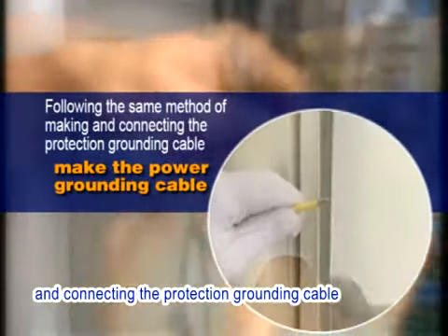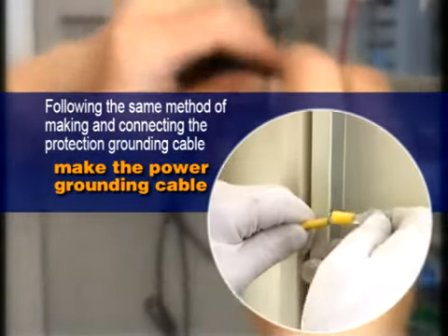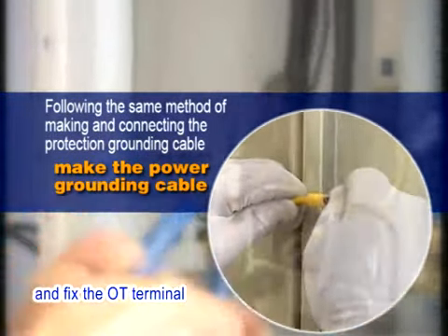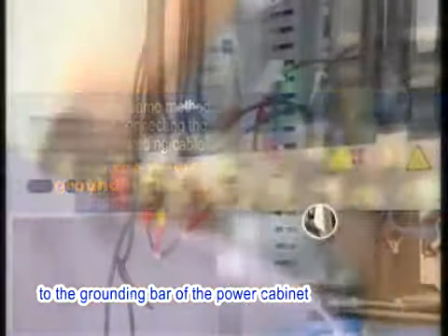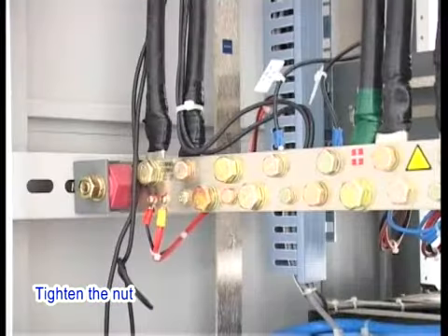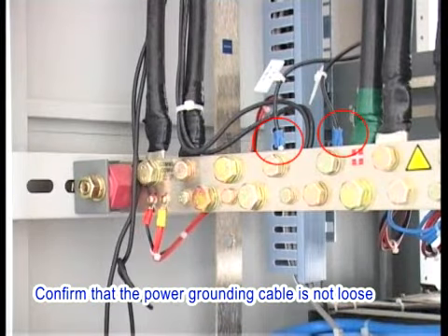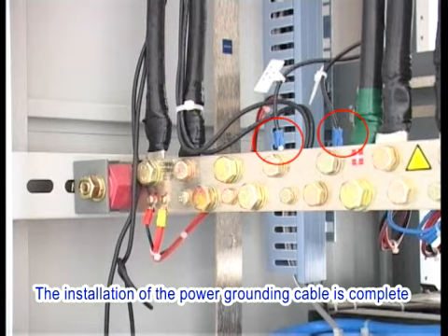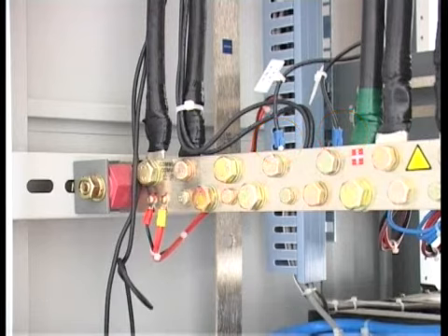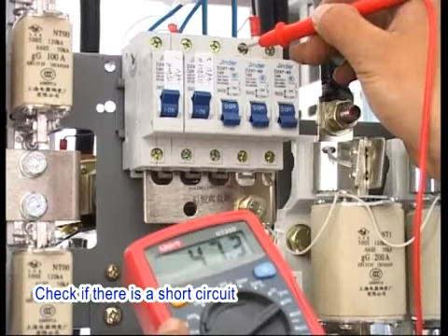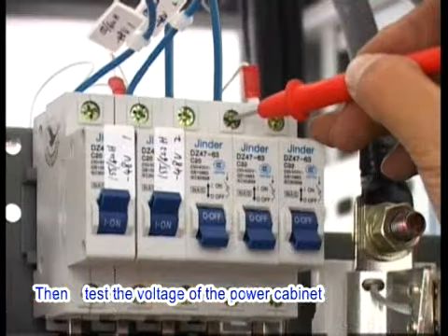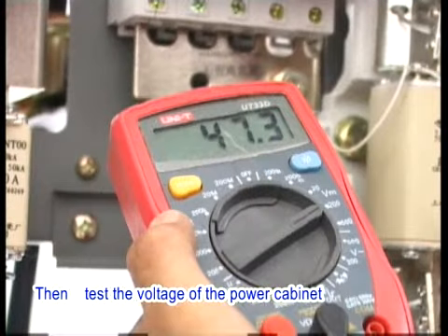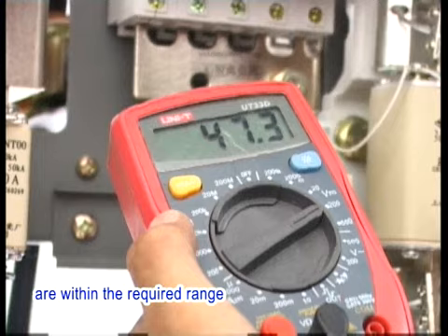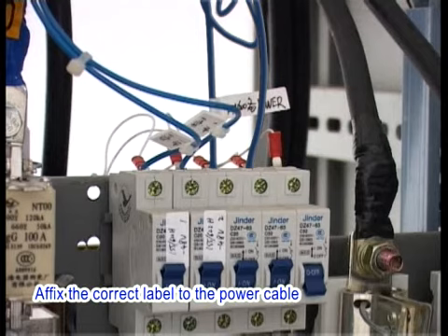Following the same method of making and connecting the protection grounding cable, make the power grounding cable and fix the OT terminal to the grounding bar of the power cabinet. Tighten the nut. Confirm that the power grounding cable is not loose. The installation of the power grounding cable is complete. Check if there is a short circuit or an open circuit in the power cable. Then test the voltage of the power cabinet to confirm that the input and output voltages are within the required range. Affix the correct label to the power cable.